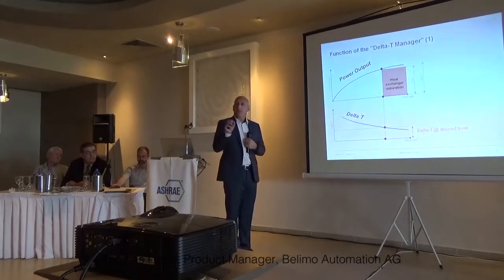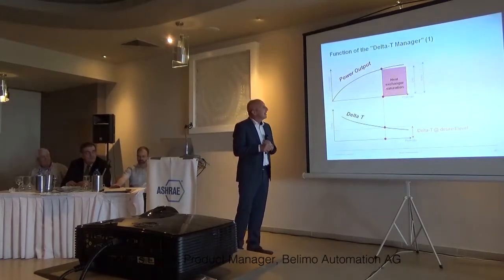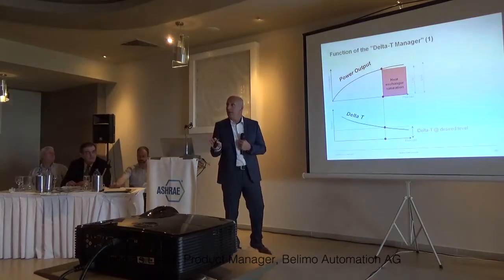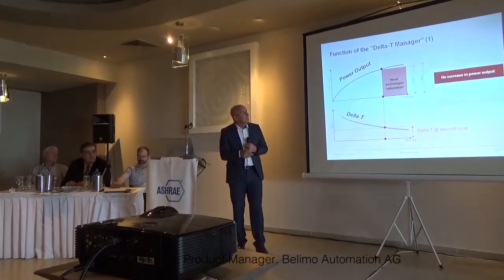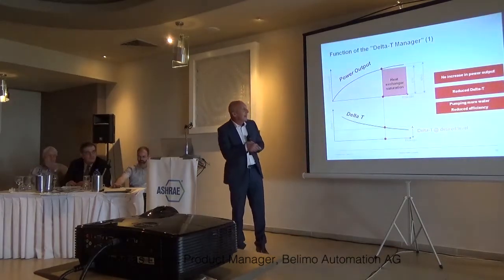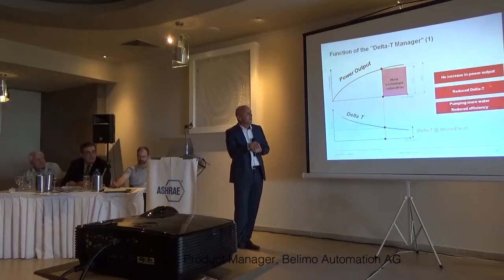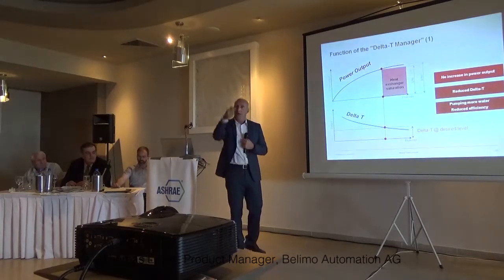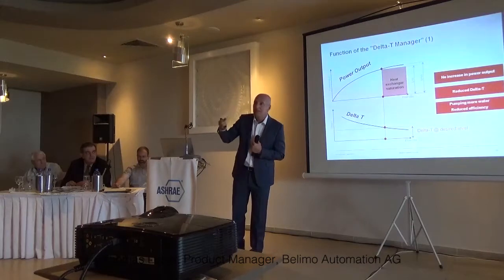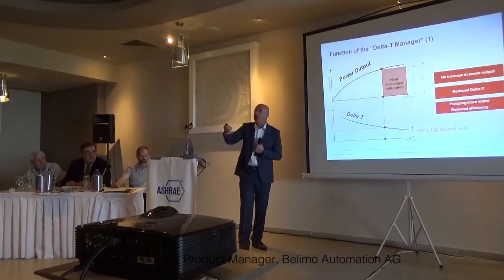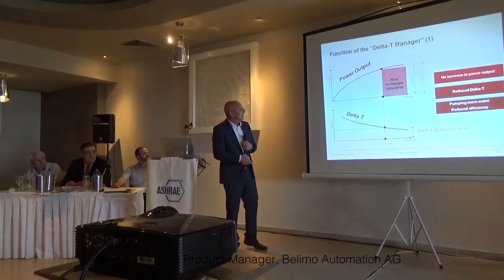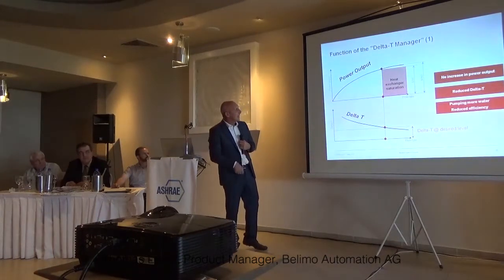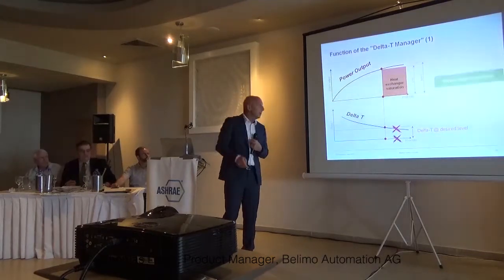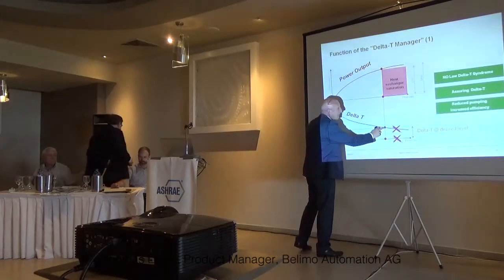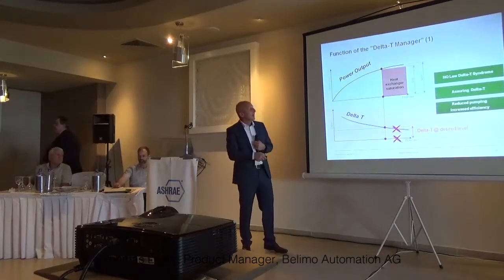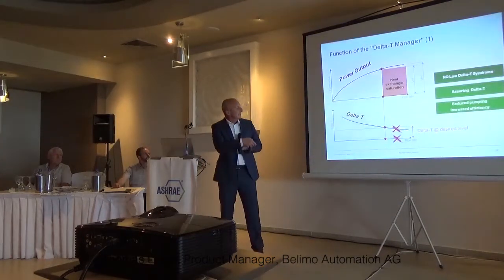This area is called heat exchanger saturation. Here, I waste money, I waste energy. There is no increase in power output, the delta T will be reduced even more, and my pumping costs go high, but it makes no sense. There is no more power going out of my fan coil. The only thing is my delta T will decrease even more. So I have to avoid that my delta T gets below a certain level.